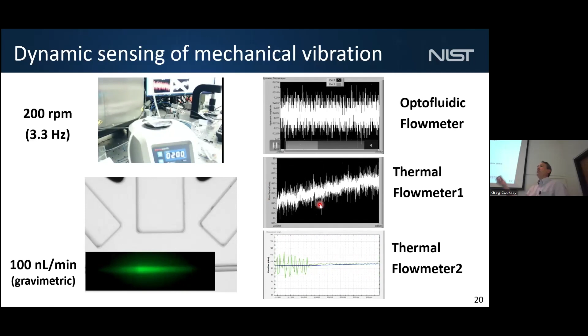We also had some fun with this. We wanted to see what we could do with this. So we hooked our flow meter tubing up to a vortexer and turned it on. And you can see how fast it can measure the dynamics of flow here. Here you can see the optofluidic flow meter measuring all of those unique mechanical vibration frequencies within that vortexer. And here's the thermal flow meter showing you that it basically has a frequency cutoff here. It drops below the measurement of the actual flow rate, which is 100 nanoliters per minute. It picks up some of the dynamics, but it's got a frequency response that's considerably damped.